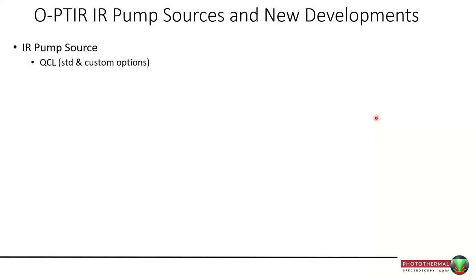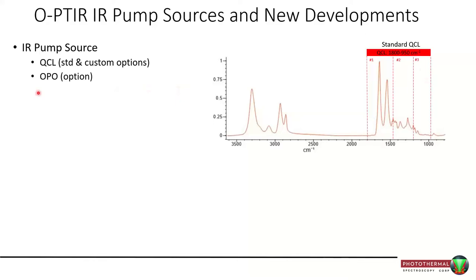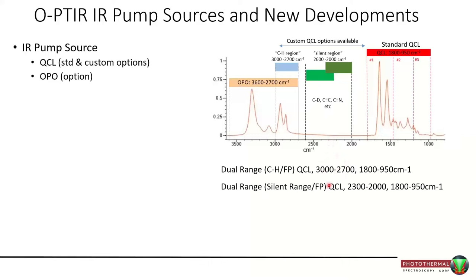At the heart of this is the QCL laser, and there have been some developments in recent years. The standard QCL covers 1800 to 950 cm⁻¹ with three chips. For higher wavenumber regions you can opt for an additional OPO laser covering 3600 to 2700 cm⁻¹. The CH chip covering 3000 to 2700 cm⁻¹ can be added as a fourth chip — up to four chips can be housed in these boxes — covering all the key functional groups in the mid-infrared spectrum. You can also opt for a silent region chip, or a low wavenumber chip going down to 800 cm⁻¹.